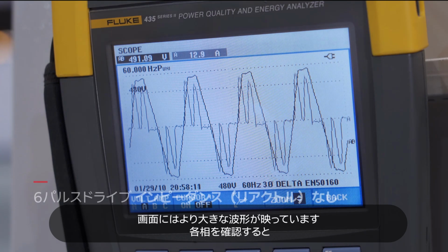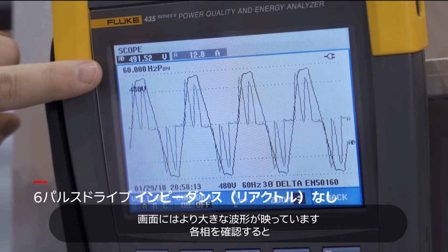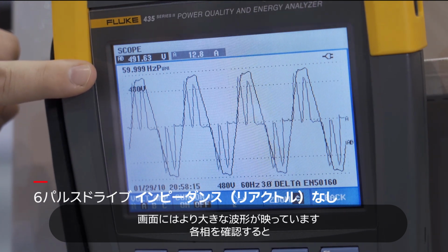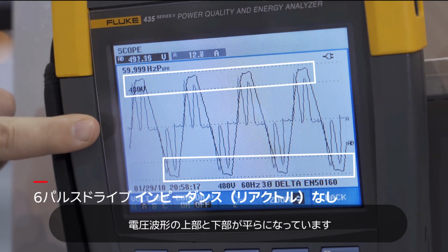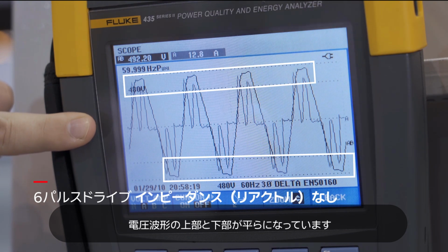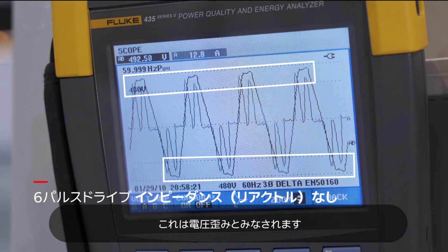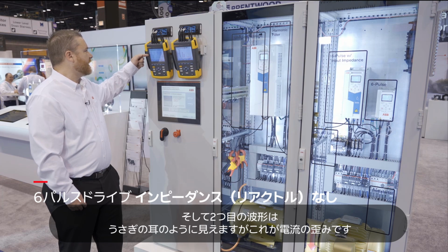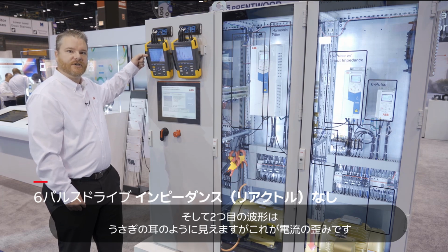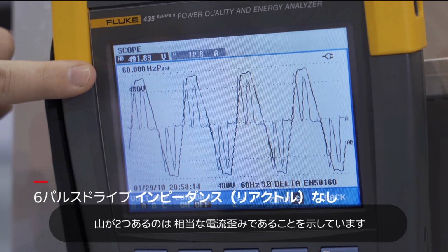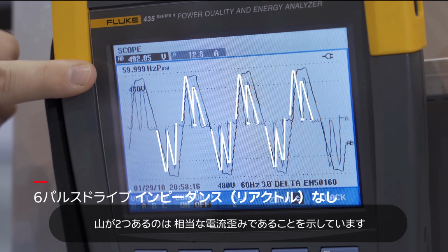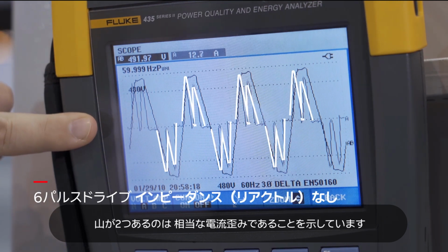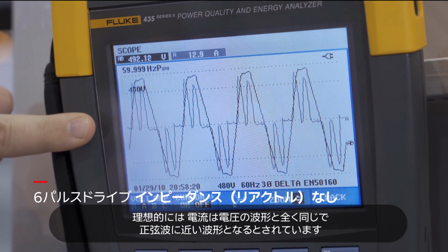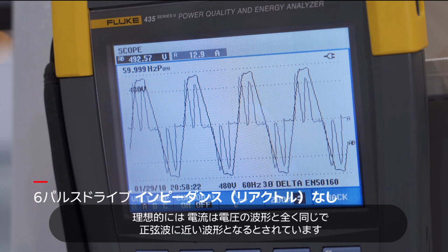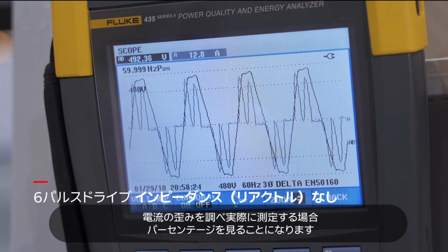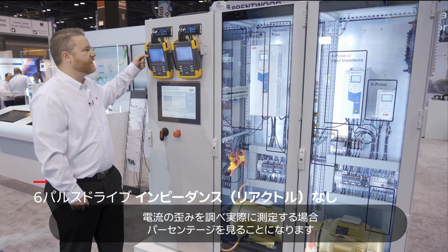And what you see here as you're looking at the image is a larger waveform. I'm looking at an individual phase right now. And I see flat topping on the top of the waveform and at the bottom of the voltage waveform. So that's considered voltage distortion. And then the second waveform, they almost look like bunny ears, is your current distortion. So when you see 2 large bunny ears like that, that's a significant amount of current distortion. Current should look just like the voltage, ideally in a perfect world, and they would model each other and be very sinusoidal. When you want to look at current distortion and actually measure it, you look at percentages.